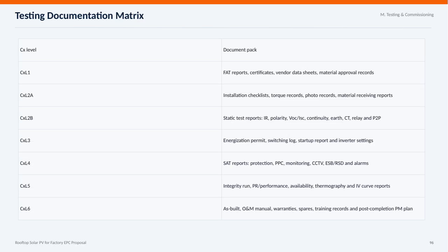Here we have the testing documentation matrix for the rooftop solar PV project. This matrix organizes the various commissioning levels from CXL1 to CXL6, each associated with a specific set of documents. At CXL1, we start with foundational materials like FAT reports, certificates, and vendor data sheets. Moving up, CXL2A includes detailed installation checklists and photo records, while CXL2B focuses on static testing reports such as insulation resistance and polarity tests. CXL3 covers critical documentation for energization permits and startup reports.